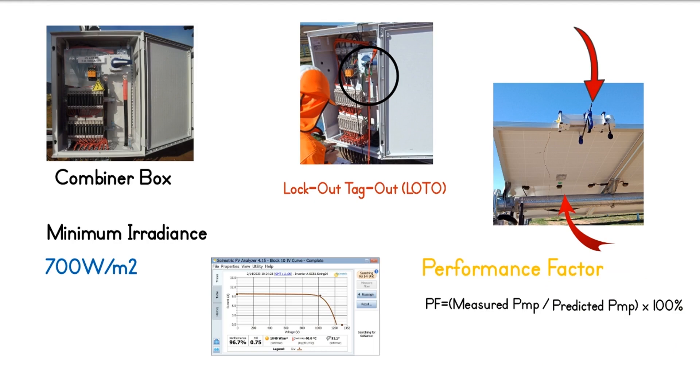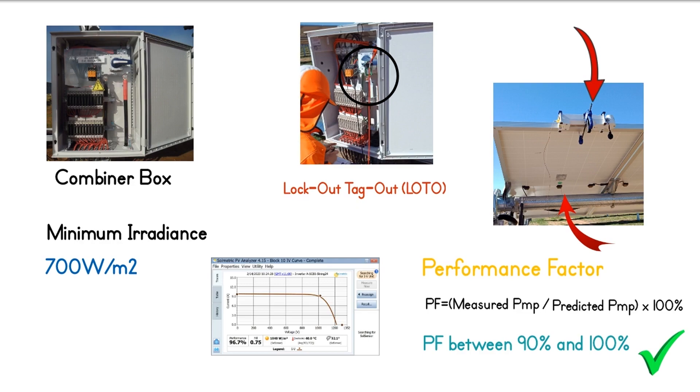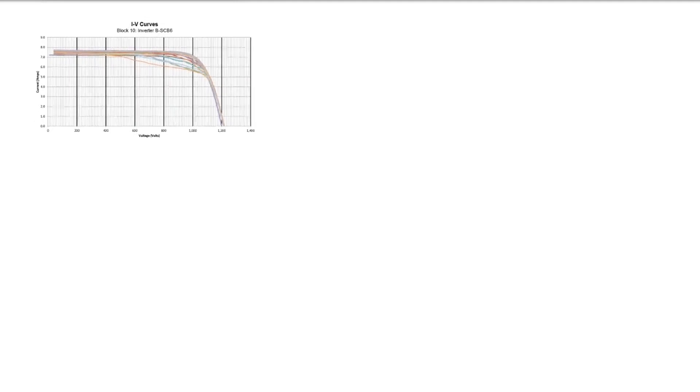In general, if the IV curve test returns a normal shaped curve and has a performance factor of between 90% and 100%, it is an indication that the string is performing correctly and is not severely soiled or shaded. Because IV curve test does not always return normal curve, we will discuss different types of deviations from the normal curve and its causes.